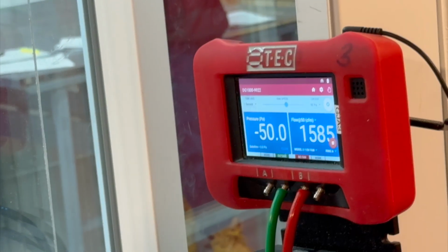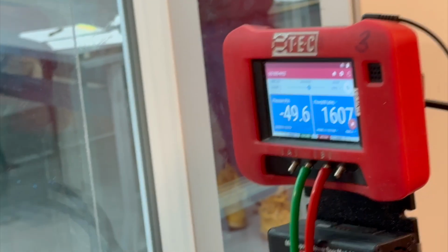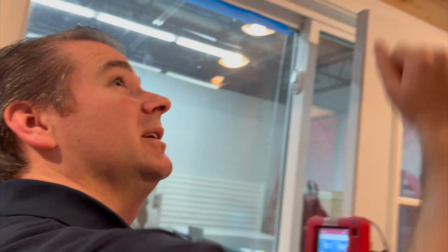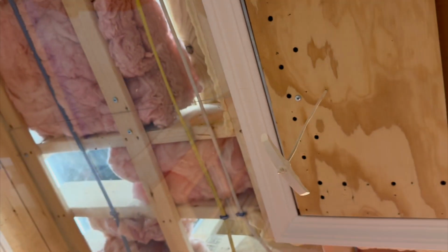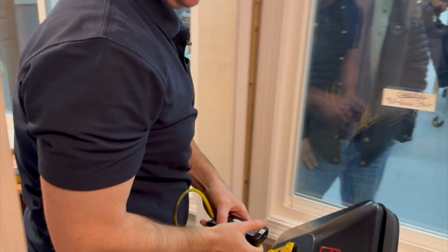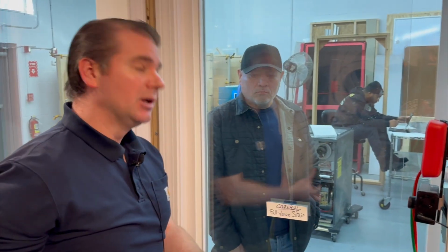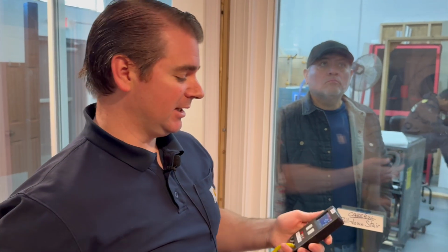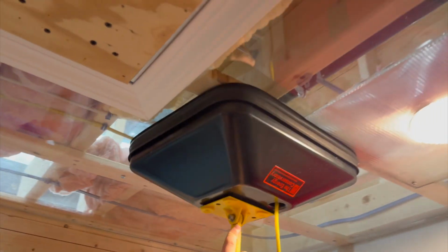All right, so our blower door CFM reading at minus 50 pascals is about 1580 CFM. Two sources of air leakage in the building in two different rooms. Attic access, we have some air leakage in that room, and around this receptacle on the wall in that room. We want to test one item that is not a duct. Test that just regular.